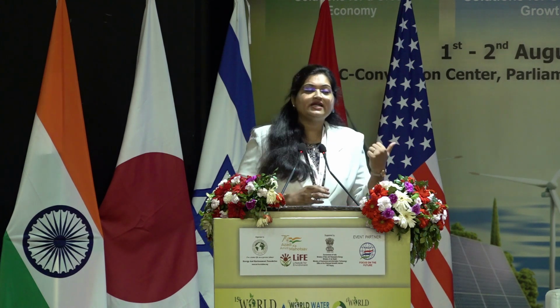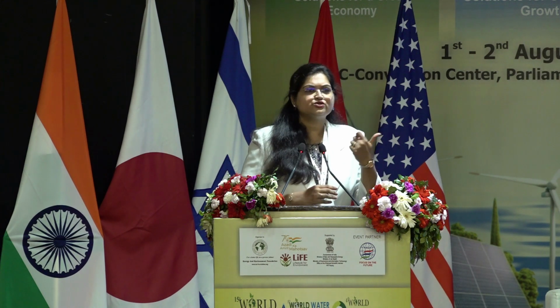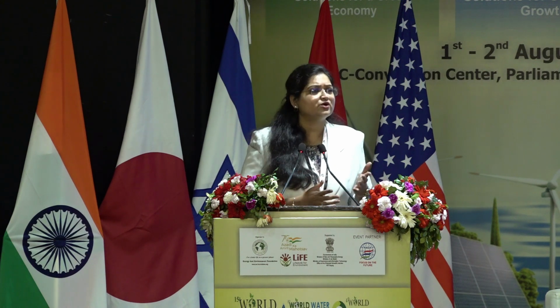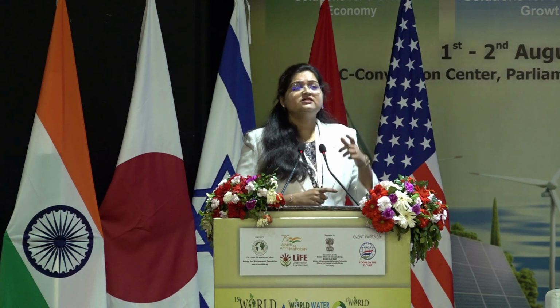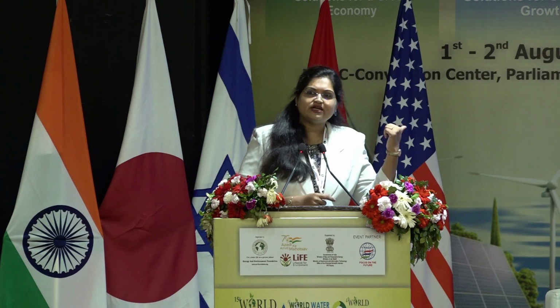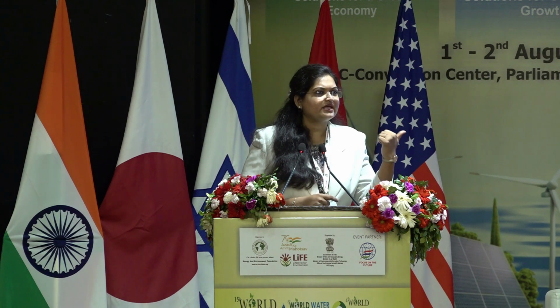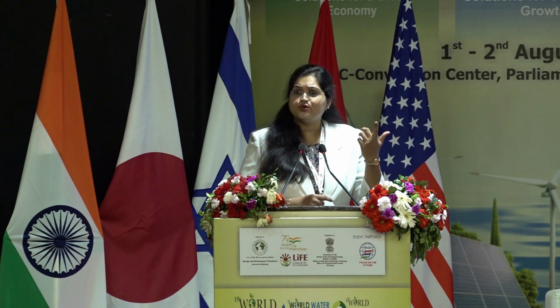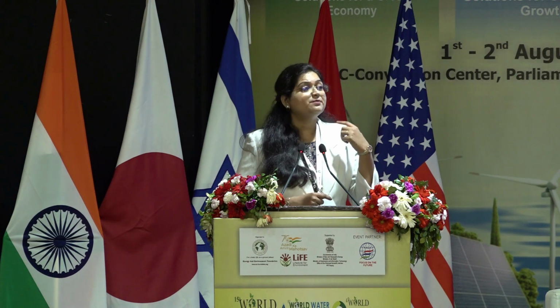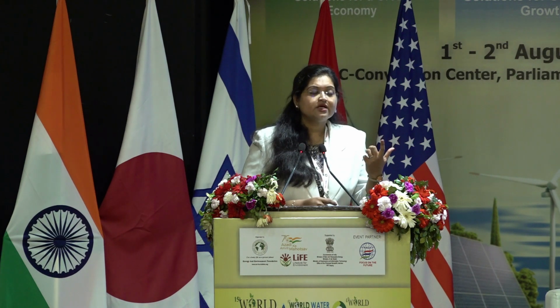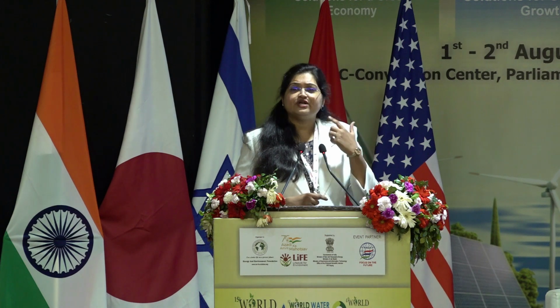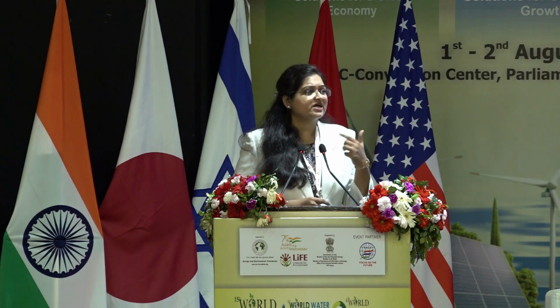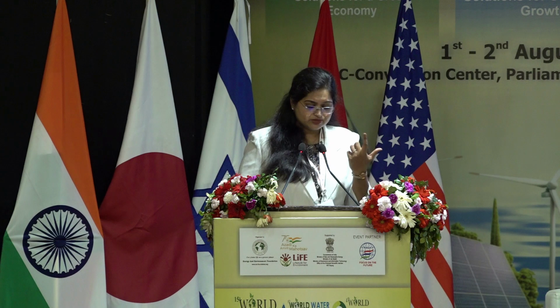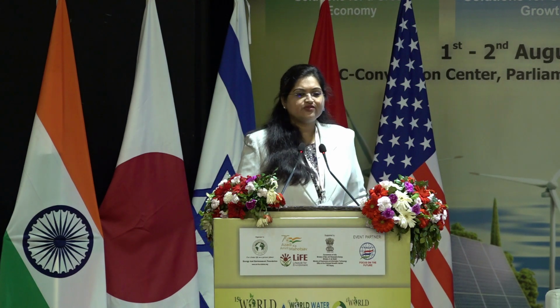In the older times, when we used to sit in the generator control turbine rooms, we would say there's a load increase, and ask what droop setting we can work with, is it 3%, 4%, and so on. But with bulk energy storage systems, the ramp up time, ramp down time, and those kinds of control schematics become very important for us.